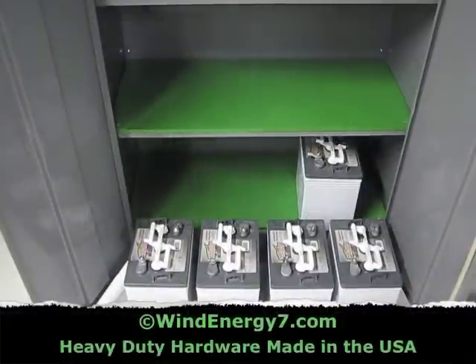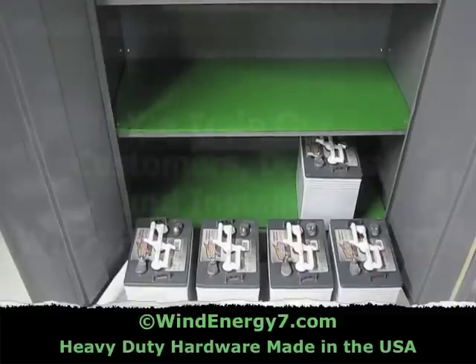Here I've got my battery cabinet reinforced in place and I'm starting to assemble the batteries and do the cabling. Usually I'll lay these batteries out like this, space them out, and try to get an idea of exact cable lengths, because I'm going to have those cables cut exactly to the right length so I've got a really nice, clean installation. I'll lay this thing out, figure out what's going where, and get ready to cut my cable length specific to the length that's needed.